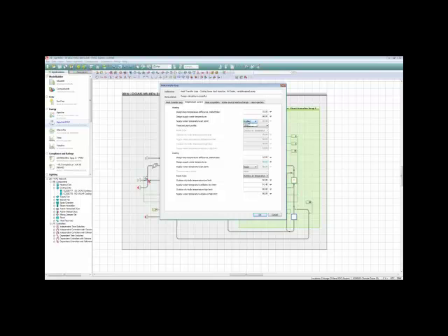So I'm going to go back to the reset, and so we've defaulted this. The most common thing would be an outdoor temperature reset, wherein as the outdoor temperature varies between 20 degrees and 50 degrees, we're going to reset this loop temperature between 68 and 53 degrees, as opposed to just using the fixed 68-degree temperature up there. Again, there's a temperature difference here, and there's something new here.